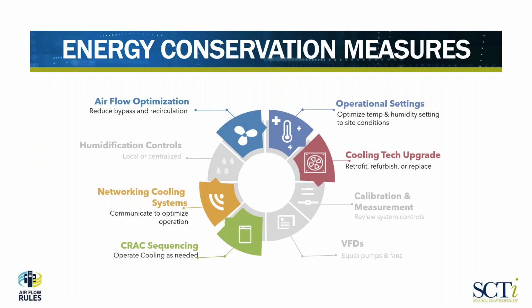So the ones I've highlighted here today are the ones that are used quite often. The airflow optimization isn't just management, which to us is the separation of cool air and warm air in the data center, but it takes it a step further into optimization: how much air do I need going to my IT equipment so I can meet the objective of the cooling optimization being the proper amount of cool air going to the IT equipment. We don't want to put excess air out there, just the proper amount required to cool the IT equipment. In a lot of cases we get into the networking of cooling systems, which leads us into sequencing of CRAC units.